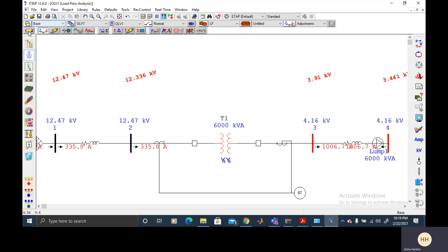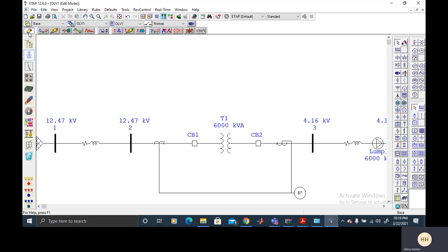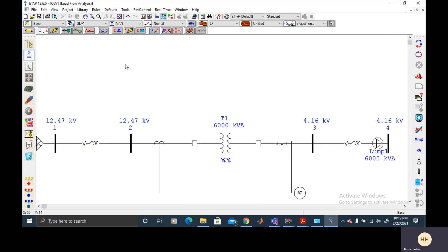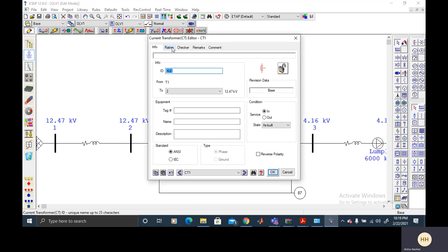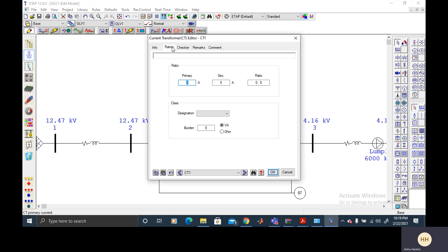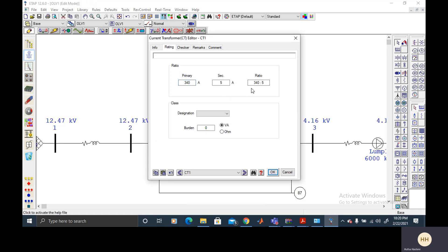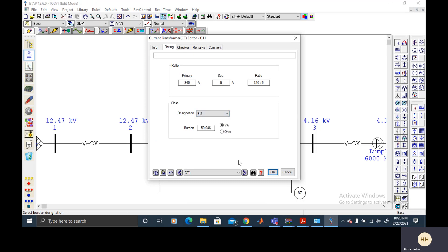So what I do is switch to edit mode and I would select the rating of this one as I had 335 ampere in my primary. So I would round this off to 340. For overload conditions it is usually 25% but I'm just rounding it off to the higher 10. And then the secondary rating is 5. I'm going to click it anywhere and it changes itself. And I'm selecting the class of this CT as B2.